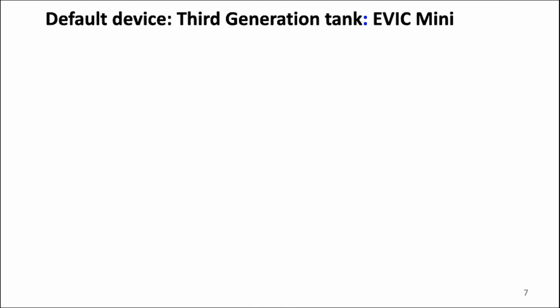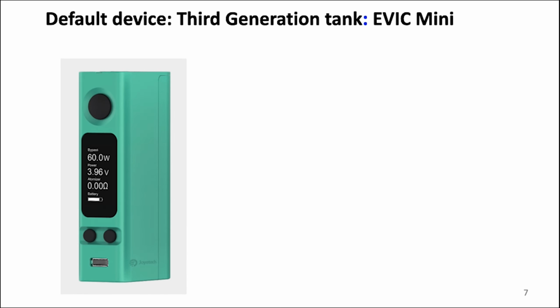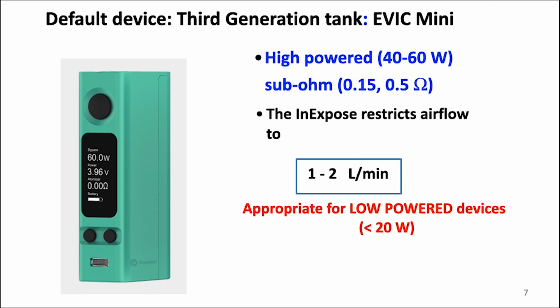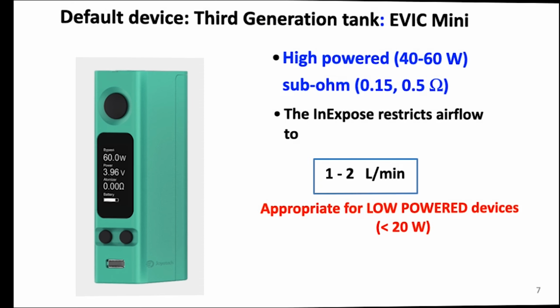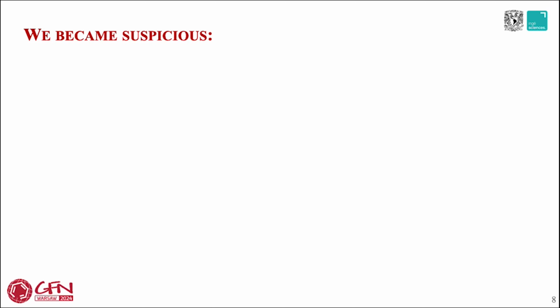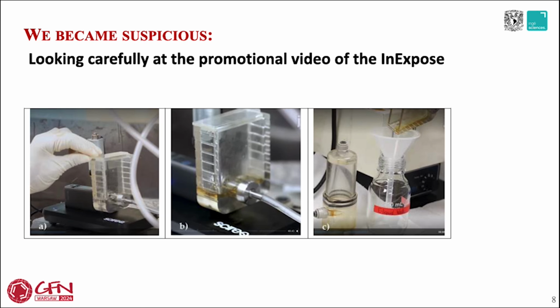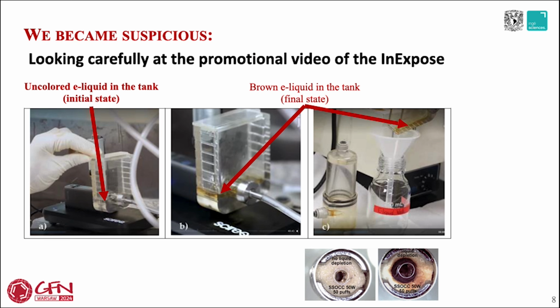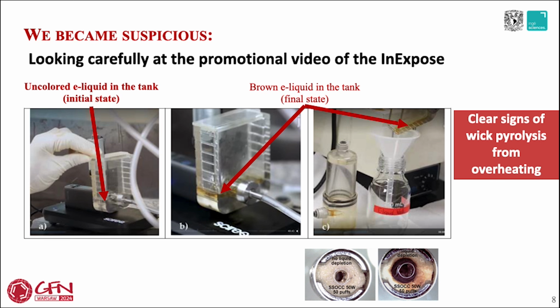The default device used by the InExpose is a third-generation tank, the EVIC Mini. It is a high-powered, sub-ohm device, and the InExpose restricts the puffing of this device to an airflow between 1 and 2 liters per minute. This is appropriate for low-power devices running below 20 watts. We became suspicious when looking carefully at the promotional video of the InExpose. At the beginning of the experiment, the liquid in the tank was colorless, but at the end of the experiment it acquired a brownish color. This is a signal of pyrolysis of the cotton wick, and it clearly shows there is overheating.